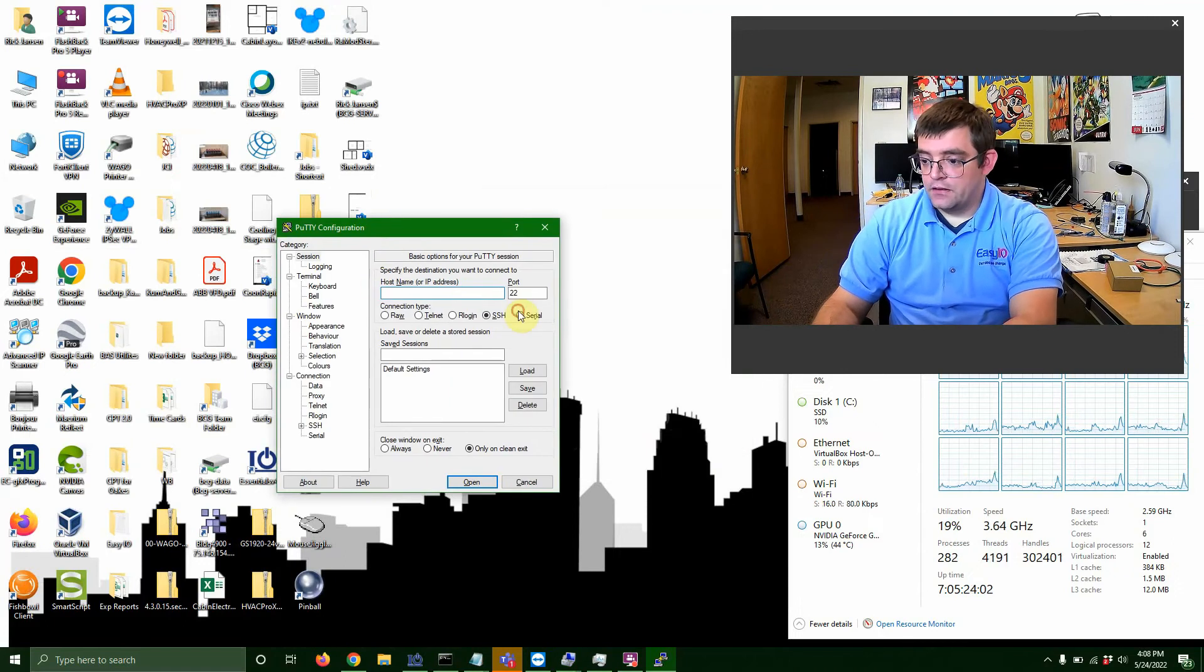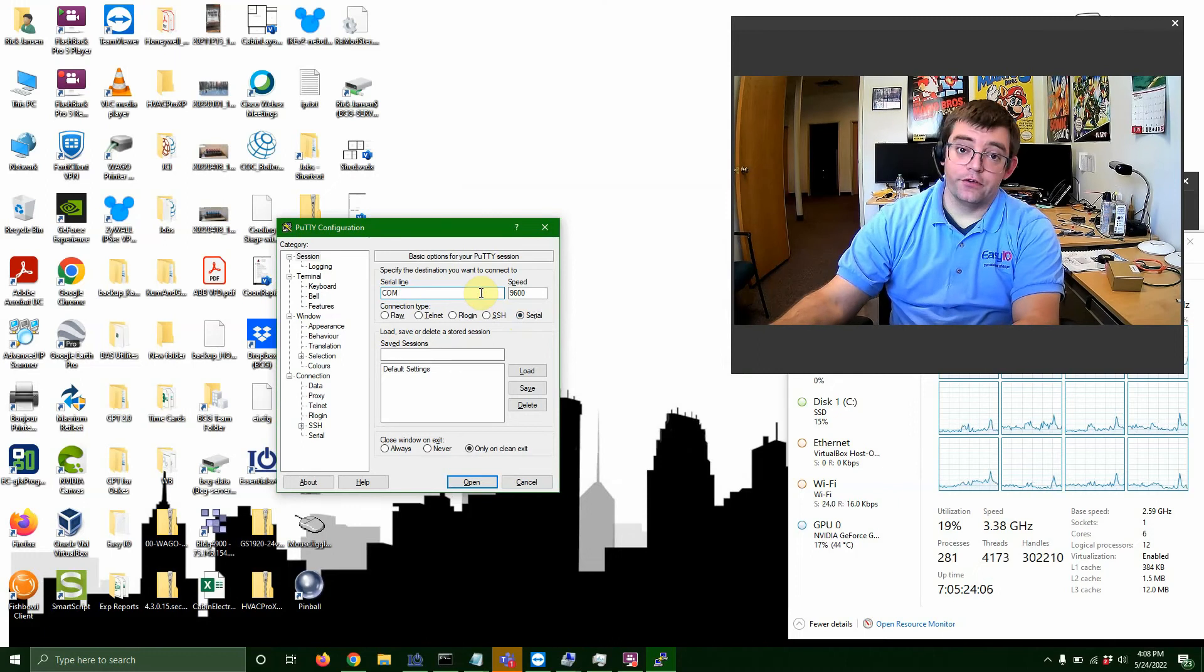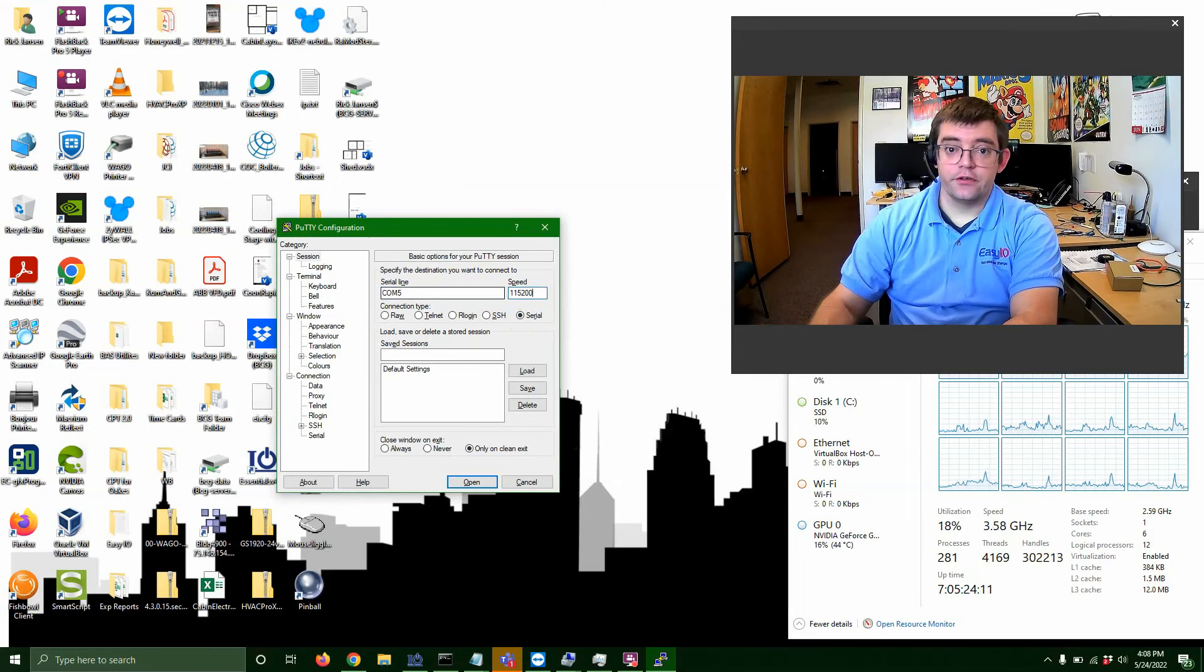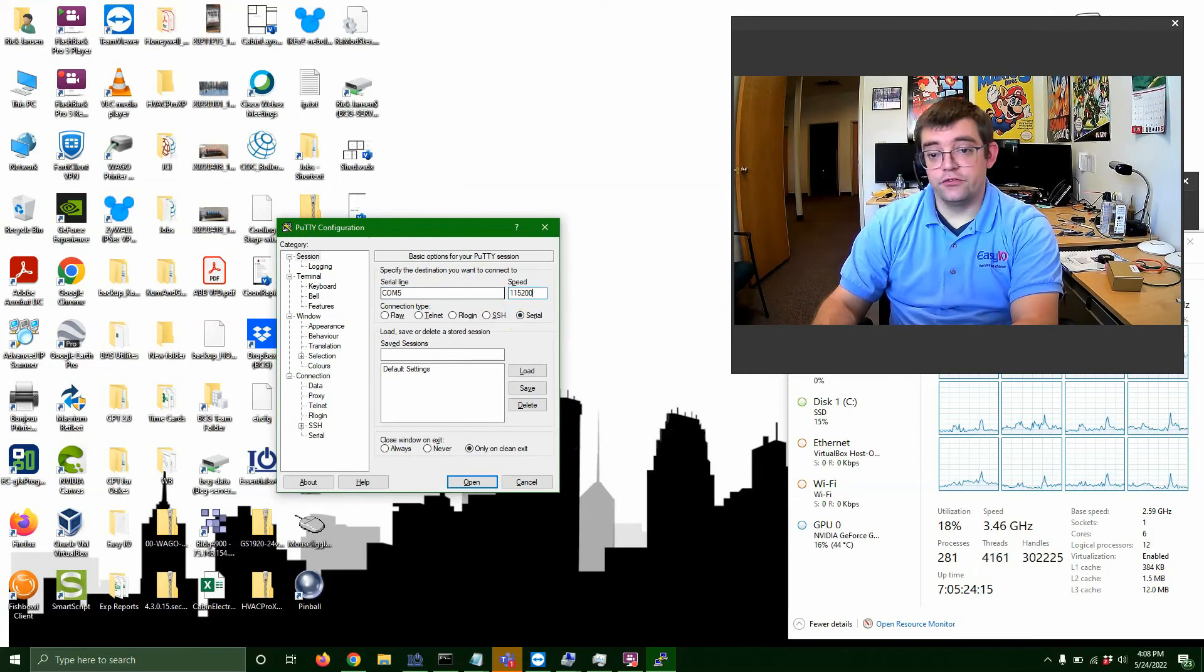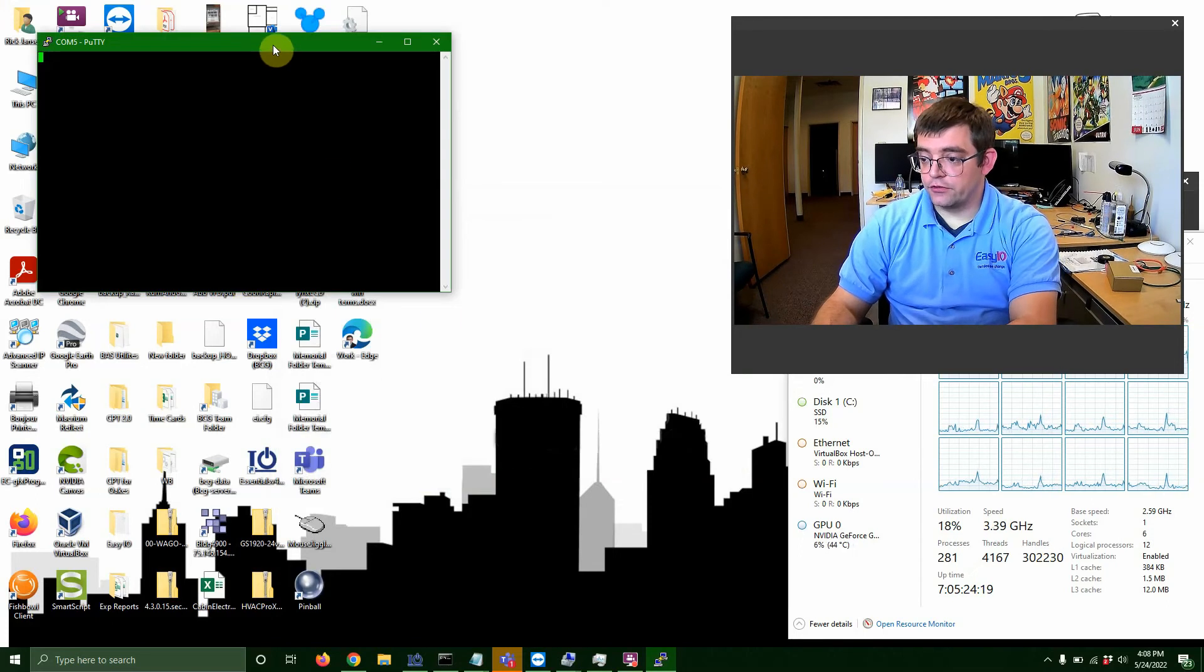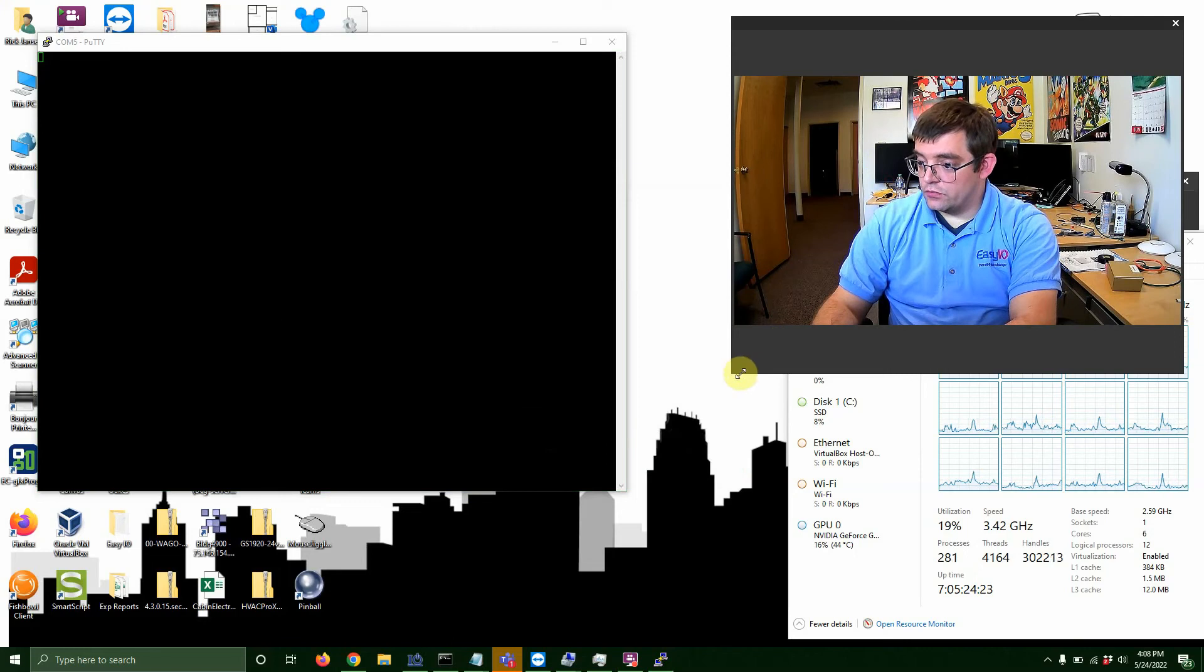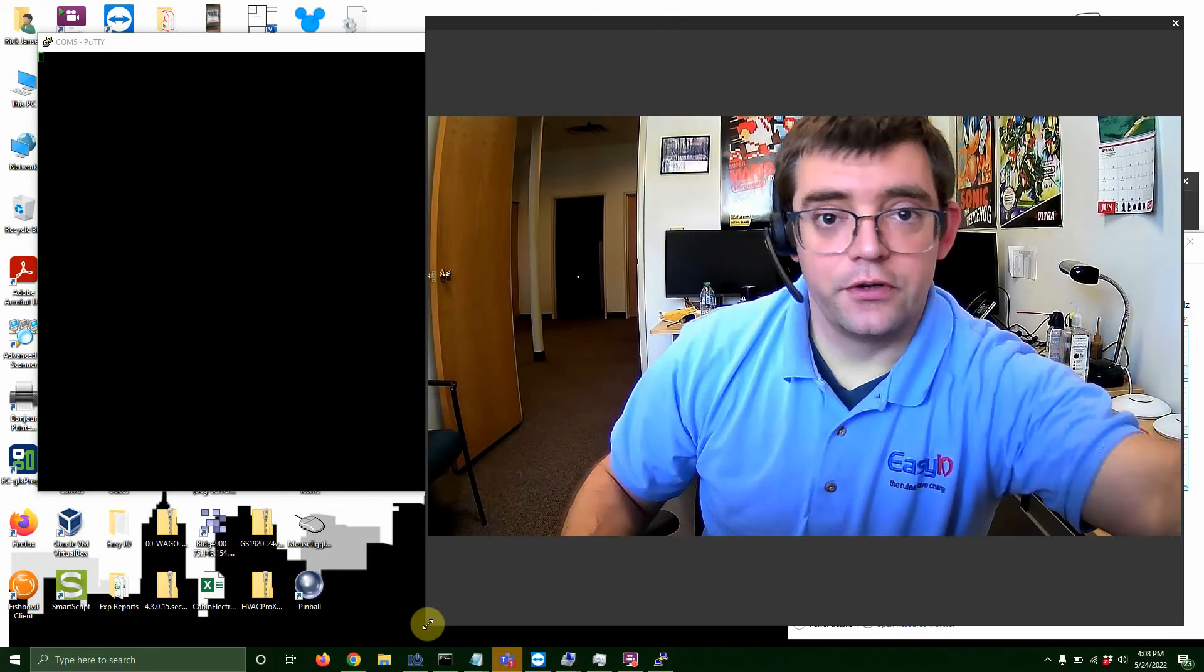And for all the Jace 8000s, it's going to be under serial. And remember, we saw comm 5 in our device manager, so we'll put that in. And 115,200 is always our baud rate, regardless of brand or Jace, as long as it's a Jace 8000. So we're going to hit open, and I see we got a blank screen here, which is what we want.